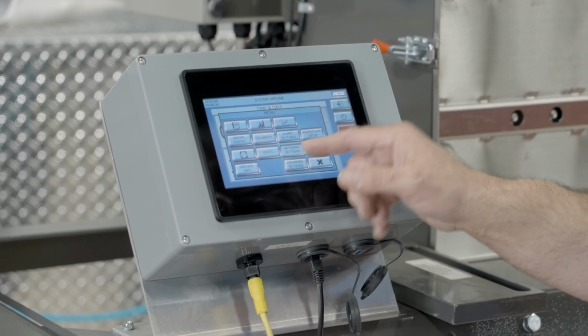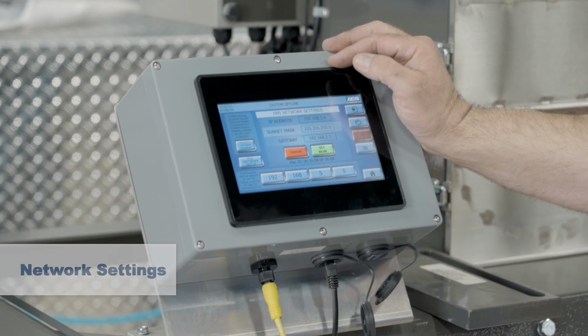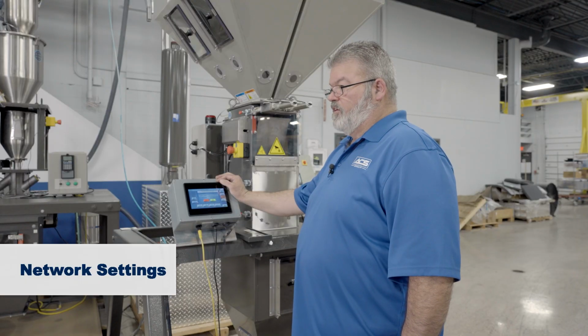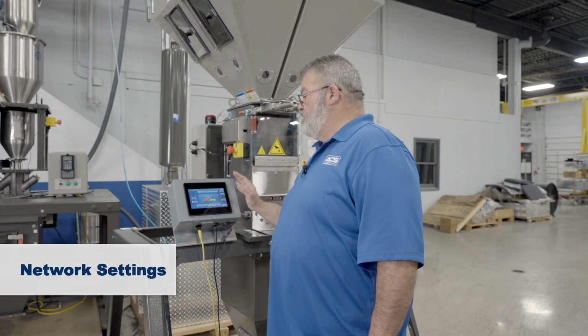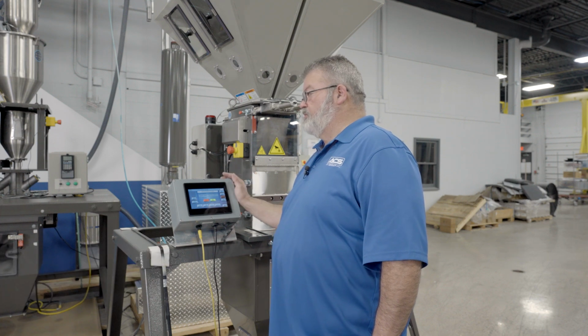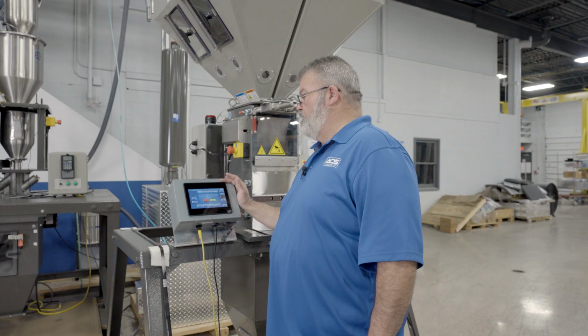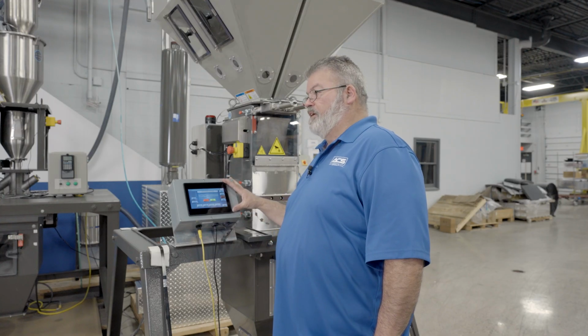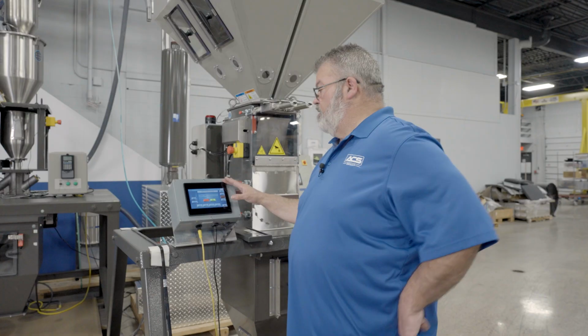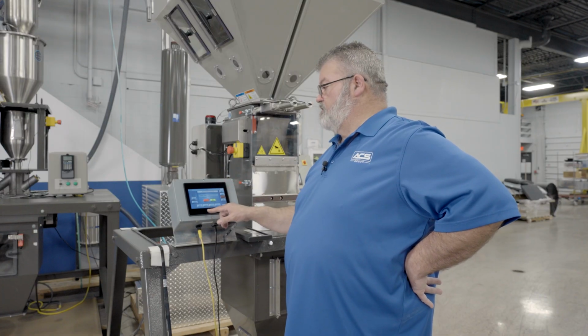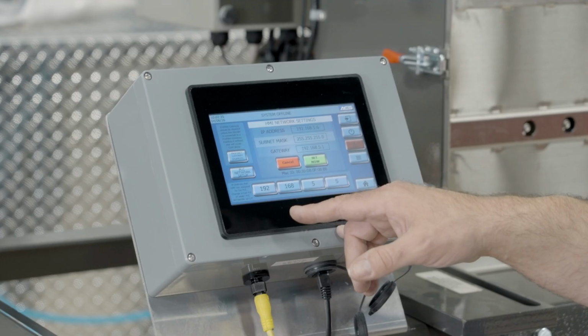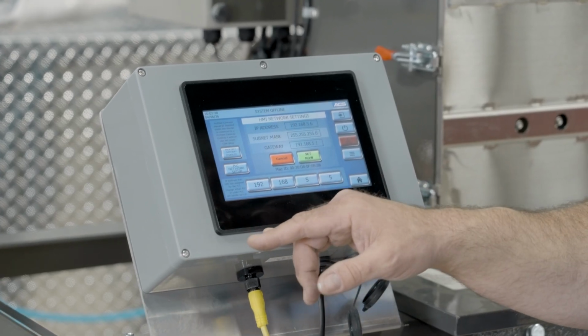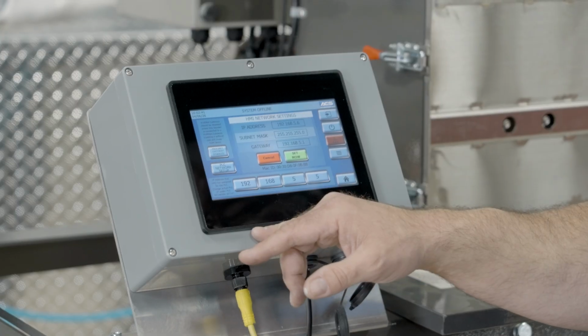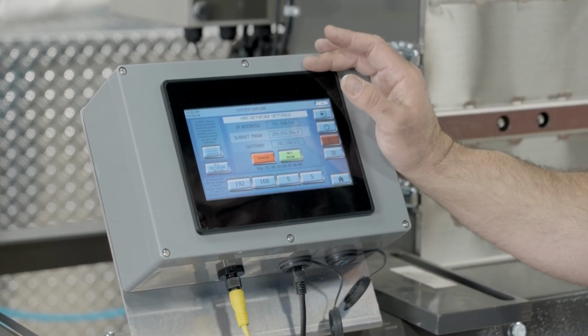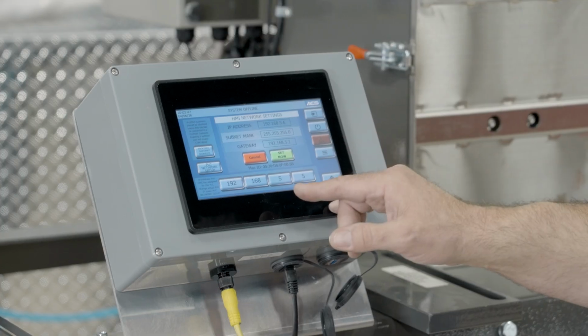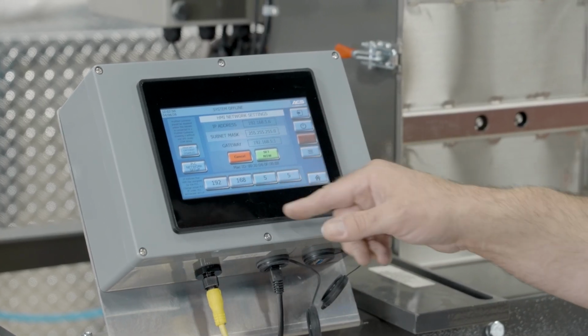Next, network settings. There's a couple different things with the network. This blender uses Ethernet, so you have a built-in server that you can communicate with and redisplay your display on your tablet or computer. You can also communicate to the PLC with a SCADA package, or we have our own package called BlendTrack and a package called MyView, so you can do data acquisition from your blender. And if you're going to do anything like that, this is where you'll set your IP address for the screen and the PLC.